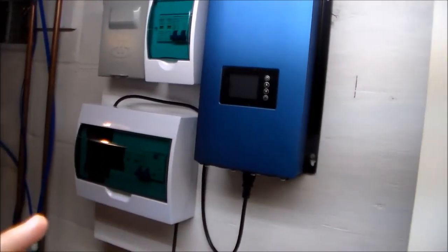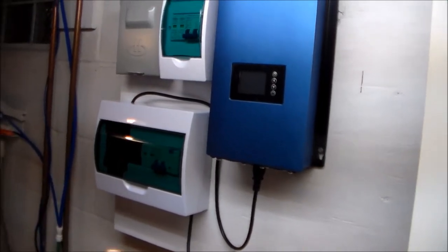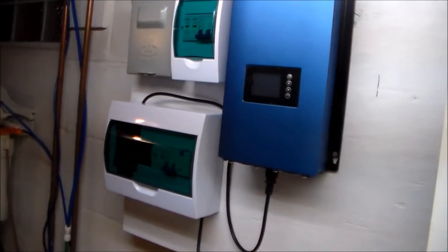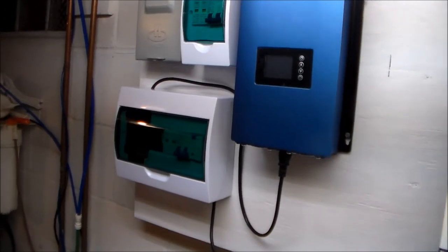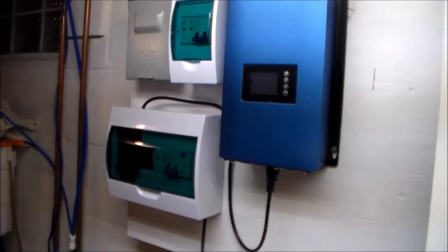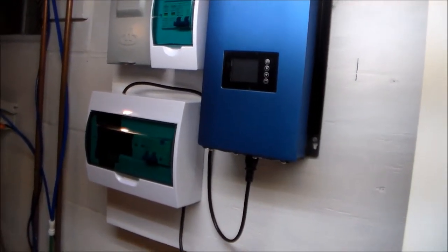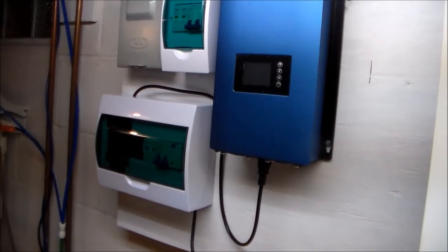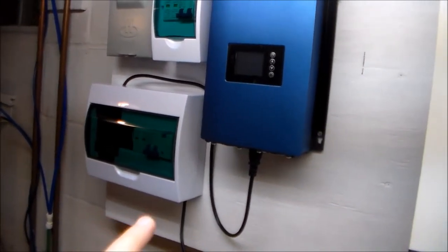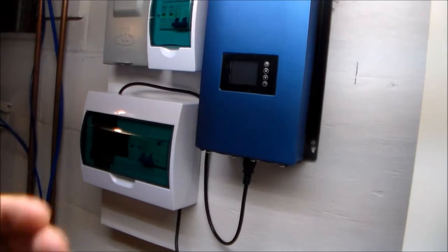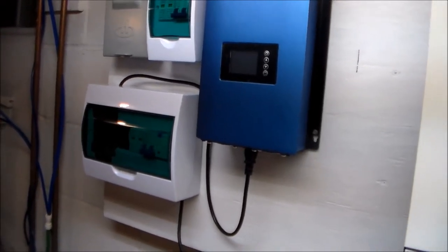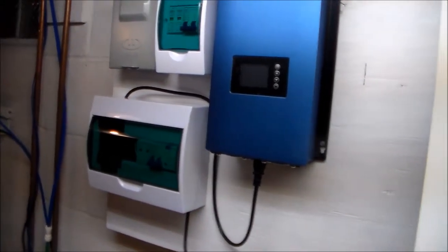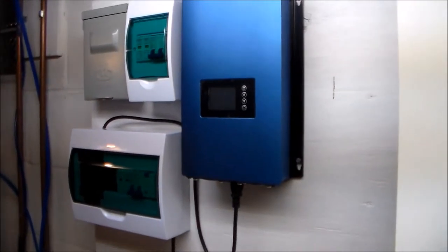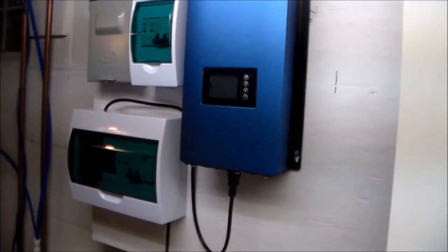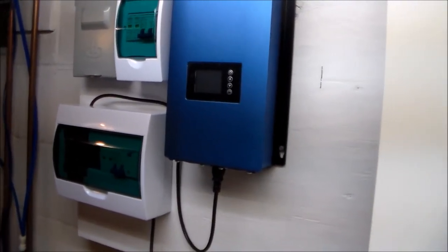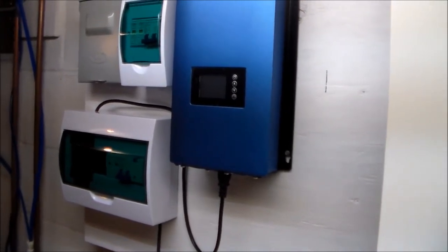To compromise and get things into the proper limits, I'm going to connect 2 pairs of the panels in series, then connect those 2 sets in parallel. That will give me 60 volts coming in at 17 amps from the panels when they're maxed out at their highest power output. Now that we know that, we can determine the wire and fuse sizes to use.